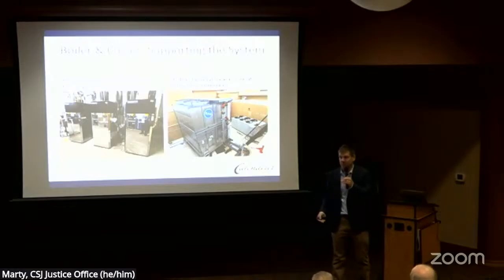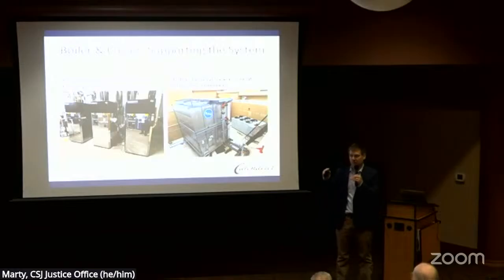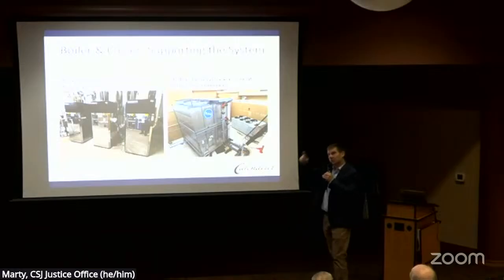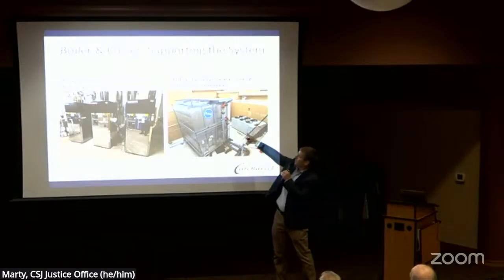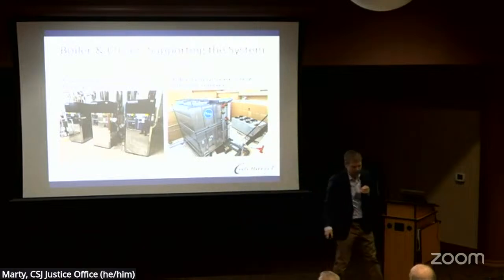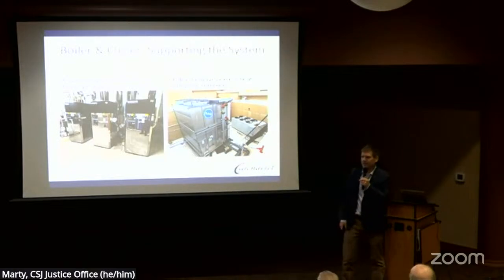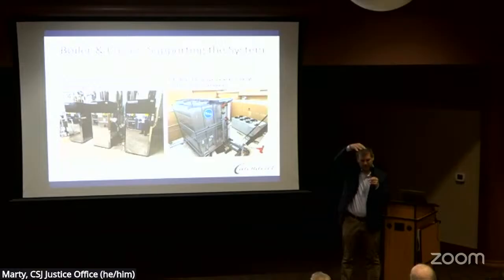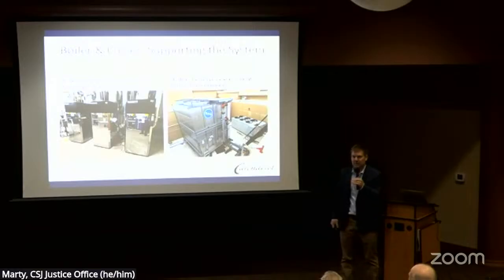On the flip side, come summertime, we don't need the heat. We're trying to keep the cooling, or that temperature, down below 85 degrees. Well, how do we do that? Almost right above us as well, there is a chiller and a cooling tower. A cooling tower is a glorified shower, if you will. It's got a big nozzle up top, and it takes water and sprinkles it over a bunch of media, and as it runs down, evaporative cooling happens, and it gives up the heat and cools down. So if you think when you get out of the shower and you're wet, you get cold — that's the same thing that's happening. It's a very basic design system that works fantastic.